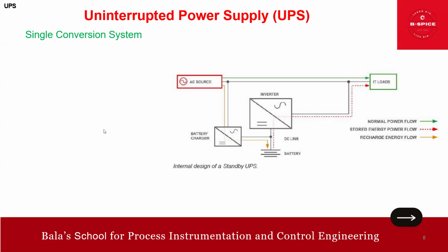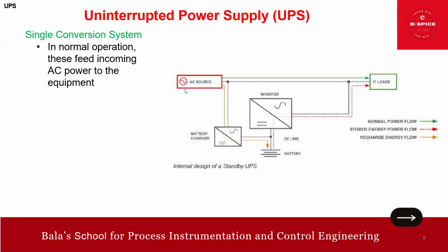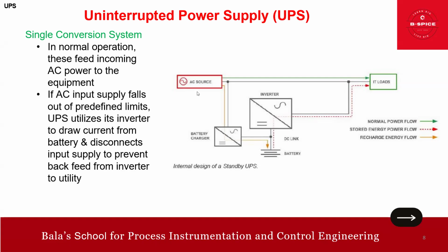In normal operation, the incoming feed supplies AC power to the equipment, as simple as that. If the AC input supply fails, the UPS utilizes its inverter to draw current from the battery, and disconnects the input supply to prevent backfeed from the inverter to the utility. That is how single conversion works.